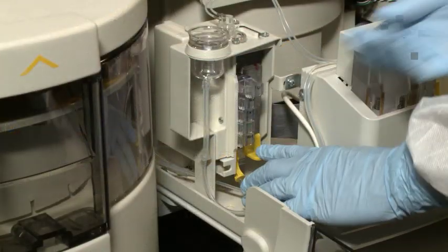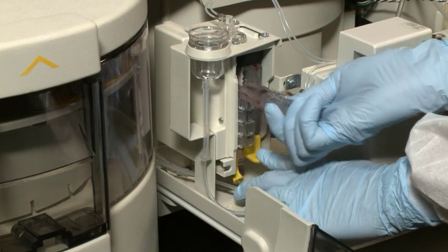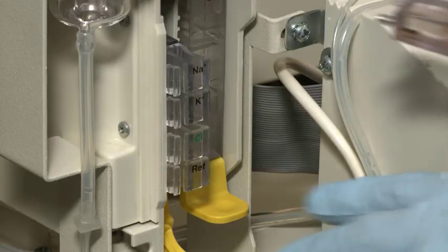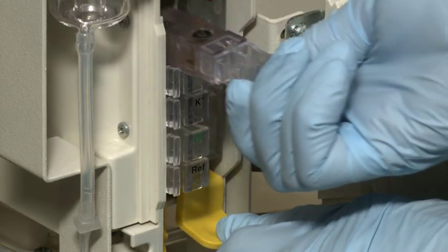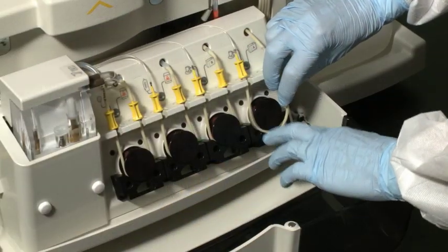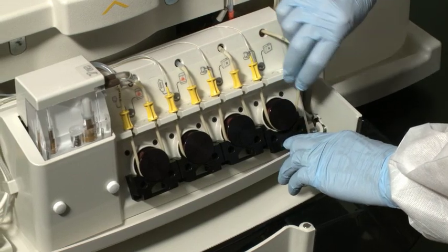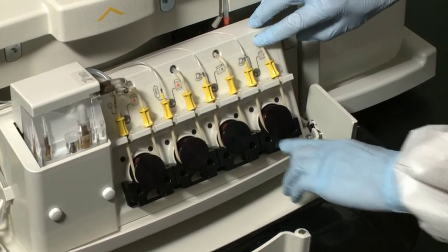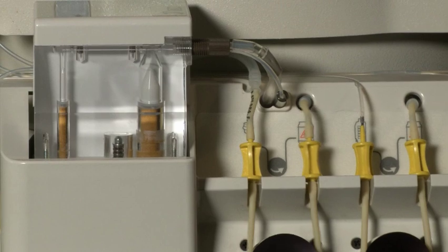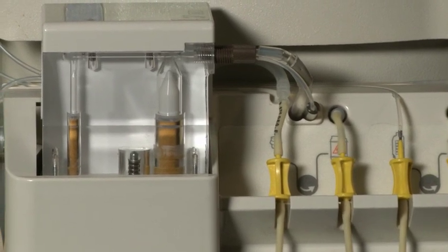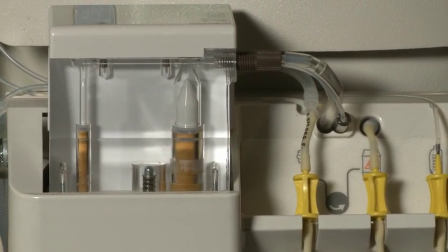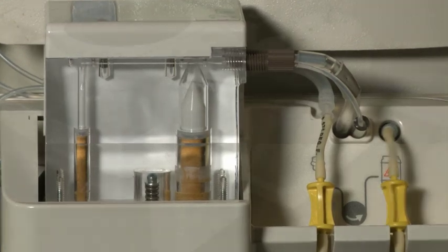The onboard ISE module is fully accessible for replacement of the economical, no-maintenance snap-in electrodes. Pump tubing and other consumables are easily replaced. The precision diluter pump seals are maintenance-free. The transparent design allows for easy inspection of solutions.